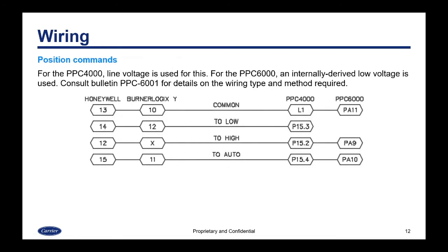Next, we have position commands. For the PPC4000, line voltage is used for this, but for the PPC6000, it's an internally derived low voltage. For the PPC6000, you want to consult the bulletin for details on the wiring type and method required, because there are some things you have to follow for the wiring method, including a special cable to use. But all of the outputs to low, to high, to auto connect to the PPC4000 and 6000 from the flame safeguard.